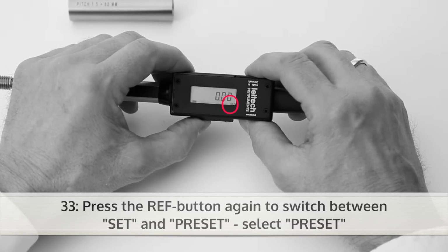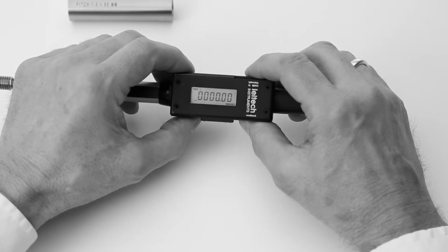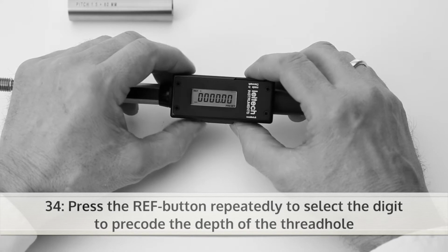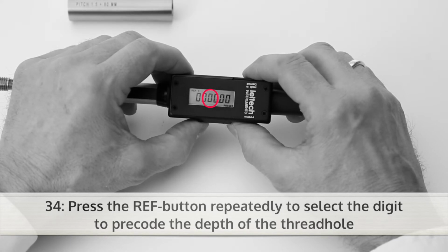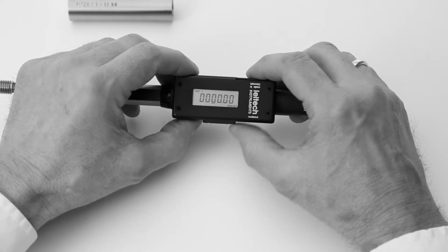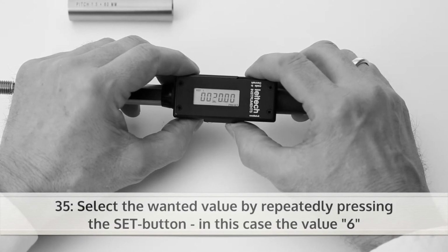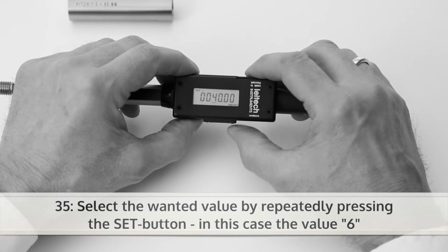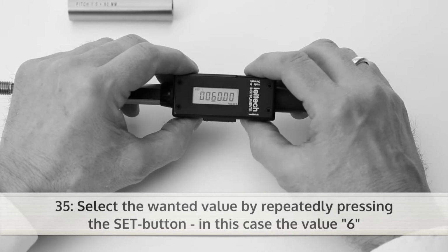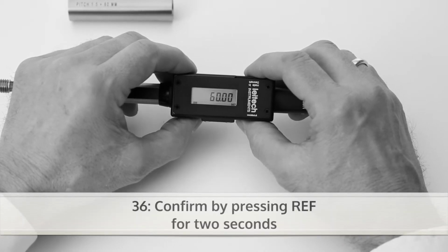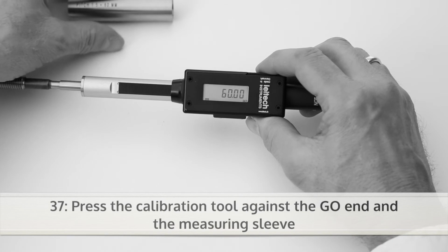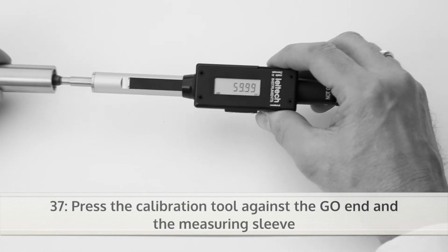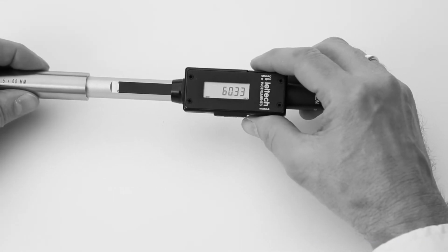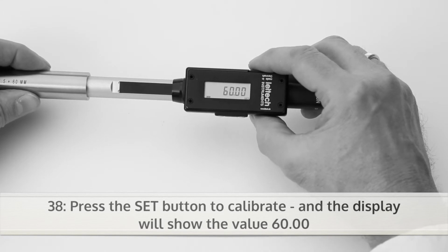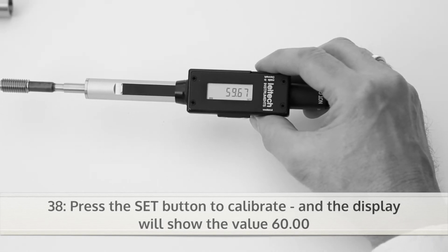Press the Ref button again to switch between Set and Preset. Select Preset. Then press the Ref button repeatedly to select the digit to pre-code the depth of the thread hole. Now you can select the wanted value by repeatedly pressing the Set button, in this case the value 6. Confirm the value by pressing the Ref button for 2 seconds. Next, press the calibration tool against the go end and the measuring sleeve, press the Set button to calibrate, and the display will show the value 60.00.